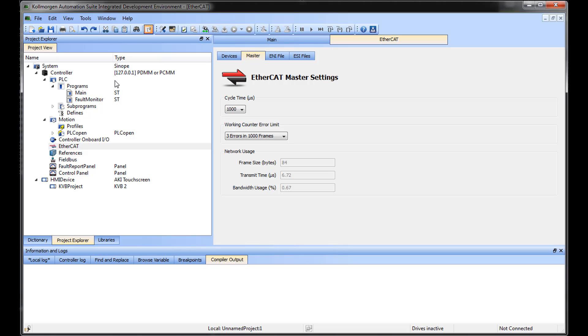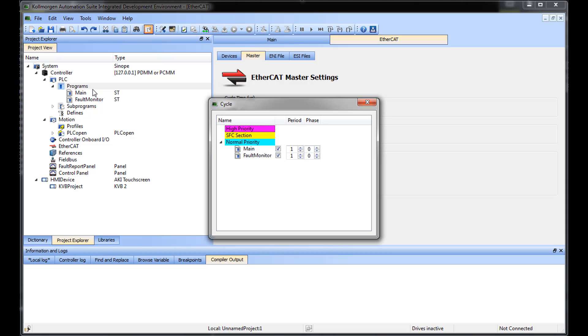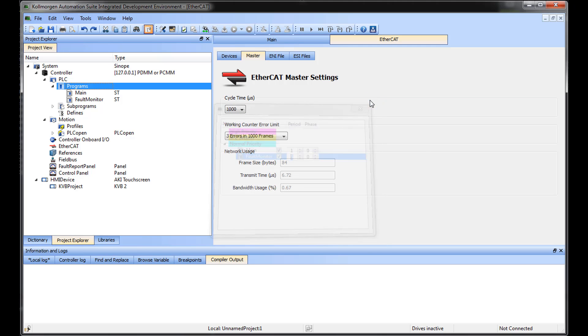Each program in the PLC code can be updated at a slower rate at a multiple of the base EtherCAT update cycle. This is set by right-clicking on the program in the project tree and selecting Cycle. Setting a five here means that the main program will execute once every five EtherCAT update cycles or scan once every five milliseconds.